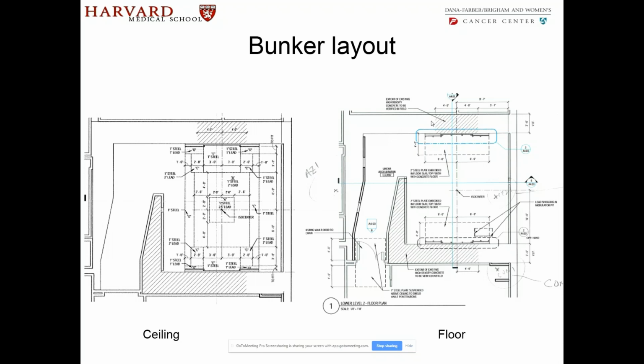If I move the mouse, can you see the mouse moving? Yes. So this is the entrance to the bunker. You go in there, and the machine will be installed here. So this is the floor. This is the isocenter of the Linac. The Linac will be placed at this point, and the gantry will rotate around this axis. Now, interestingly enough, this is the place where I'm talking from. So if the gantry points towards me, I want to make sure that I don't get any radiation during the day because that's where my office is located.